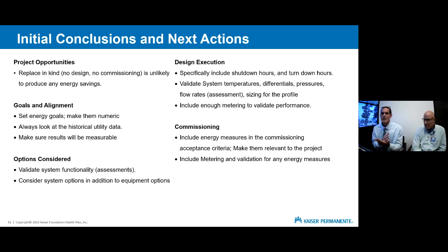During design, we almost have at this point a checklist of things to execute on. What spaces are shutting down at night? What spaces could be shutting down at night? Those are low-cost or no-cost, programming-only changes just to start taking zones down at night, turning them down at night. Make sure your design is very cognizant of the system temperatures, differentials, pressures, and flow rates - work with what's actually there in the building, not what's on the old set of plans.